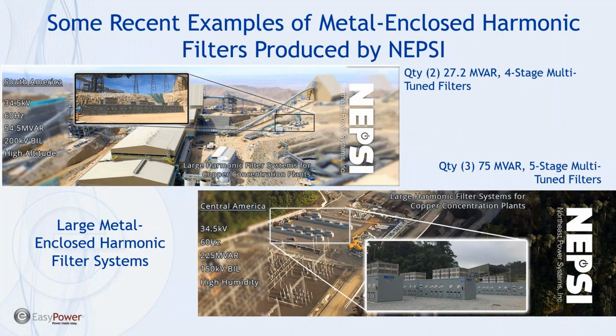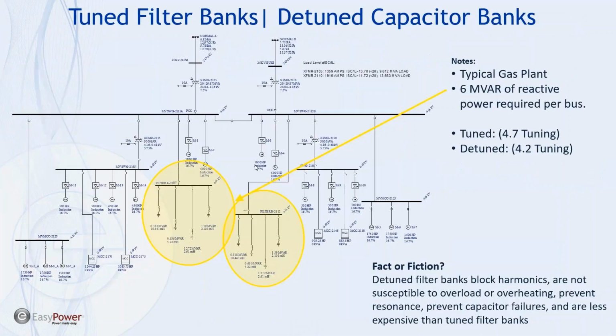Down on the bottom, we also show another large harmonic filter system consisting of 3 banks, each of those rated 75 megavars, 5 stages. So this represents, I would say, the large end of the products. We do sell smaller harmonic filters, those at the 4, 5, 6 MVAR range, but all medium voltage, 2.4 to 38 kV with impulse levels between 60 kV and 200 kV BIL.